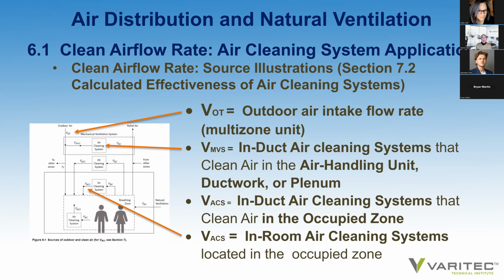There are multi-zone units that would serve a number of zones that can have air cleaning technologies embedded in them, such as their filtration technology, UVC lighting, possibly ionization strategies. There are other air cleaning technologies that are zone specific, that are served only by the return air from that one zone, and the supply air is then delivered to that zone. And then there are in-room air cleaning systems also available.